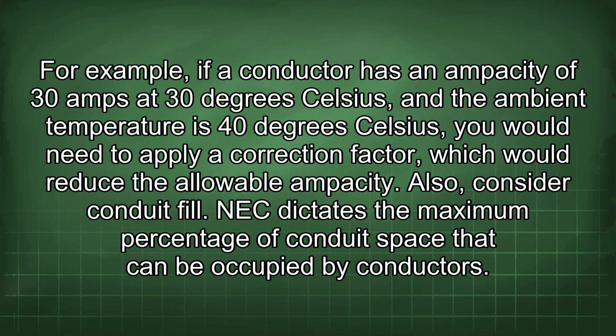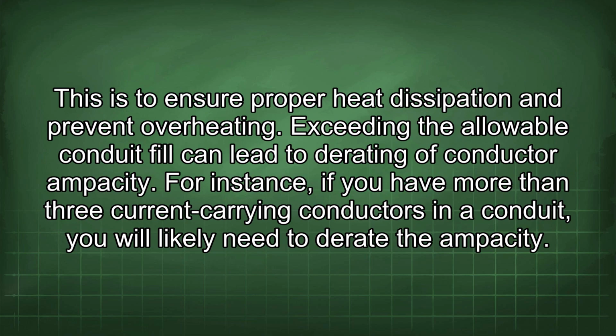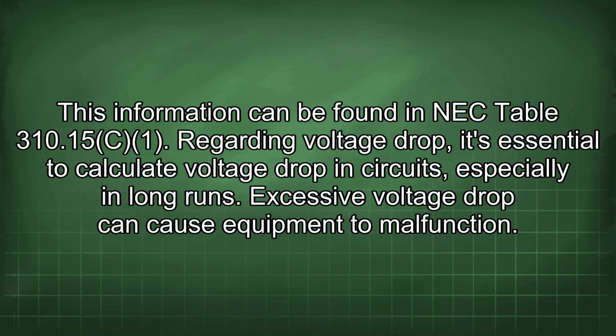Also, consider conduit fill. NEC dictates the maximum percentage of conduit space that can be occupied by conductors. This is to ensure proper heat dissipation and prevent overheating. Exceeding the allowable conduit fill can lead to derating of conductor ampacity. For instance, if you have more than 3 current-carrying conductors in a conduit, you will likely need to derate the ampacity. This information can be found in NEC Table 310.15.